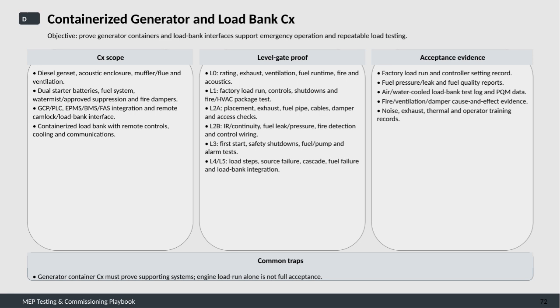The level gate proof process is structured in several stages. Starting with L0, we verify ratings, exhaust, ventilation, fuel runtime, fire protection, and acoustics. L1 involves factory load runs, control system checks, shutdown functions, and testing the fire and HVAC packages. L2A and L2B focus on physical placement, piping, cables, damper operations, inspection for leaks, pressure tests, fire detection, and wiring continuity. L3 tests the first startup, safety shutdowns, fuel pump function, and alarms. Finally, L4 and L5 cover load stepping, source failure responses, cascade operation, fuel failure scenarios, and load bank integration.